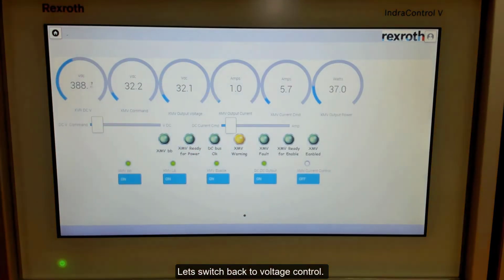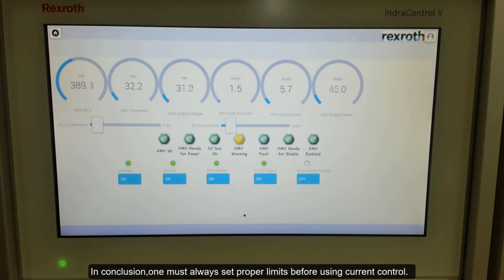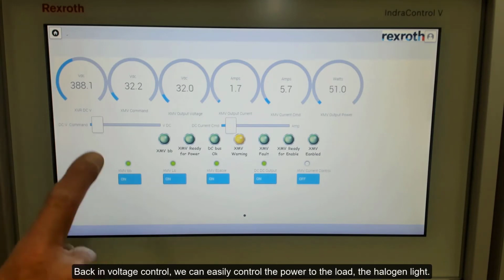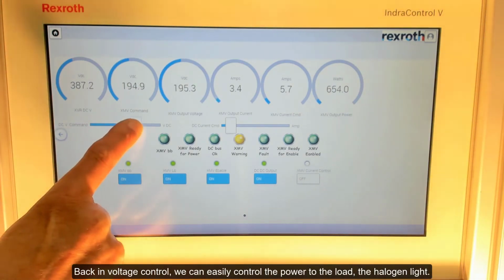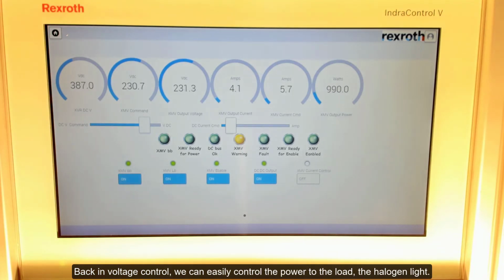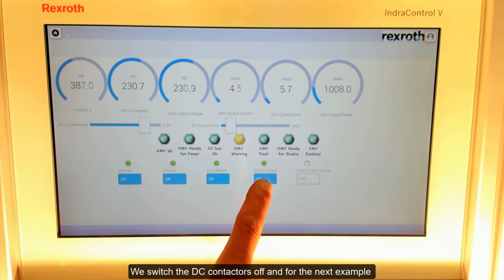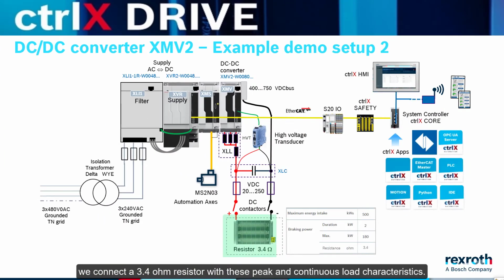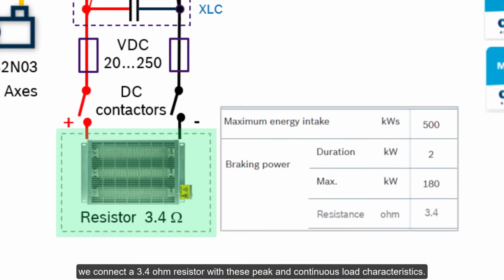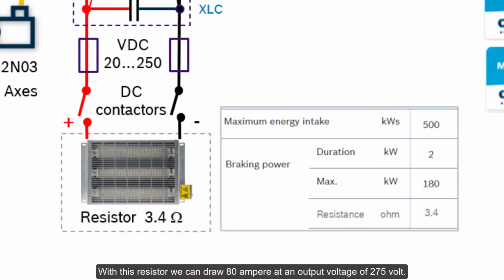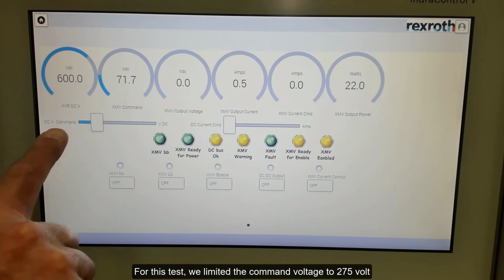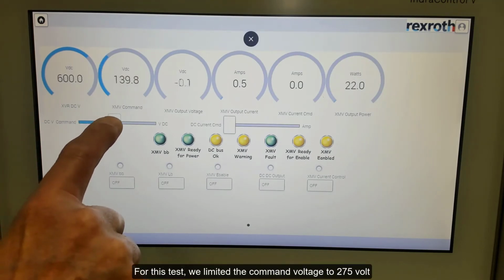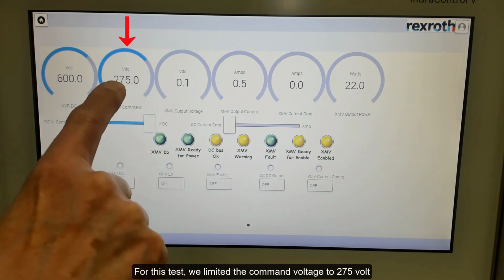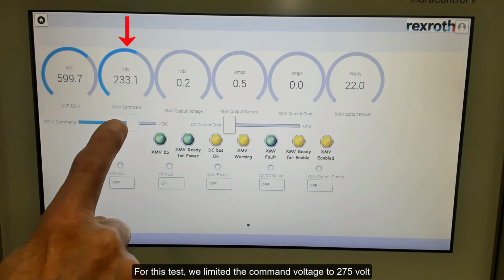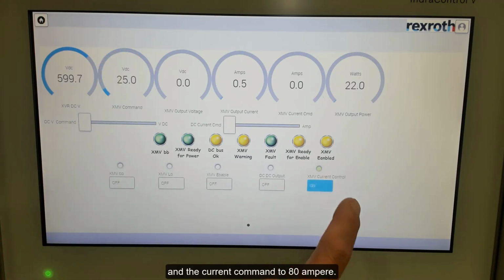Let's switch back to voltage control. In conclusion, we must always set proper limits before using current control. Back in voltage control, we can easily control the power to the load, the halogen light. We switch the DC contactors off, and for the next example, we connect a 3.4 ohm resistor, with these peak and continuous load characteristics. With this resistor we can draw 80 ampere at an output voltage of 275 volt. For this test, we limited the command voltage to 275 volt. And the current command to 80 ampere.